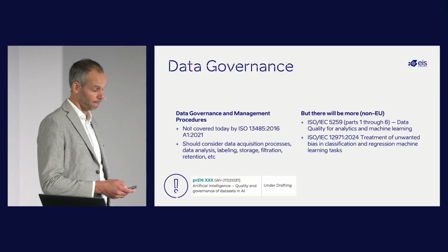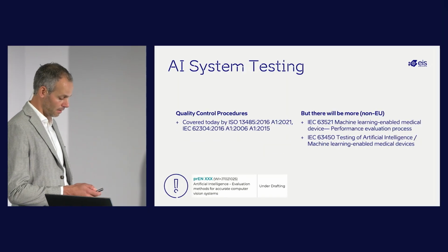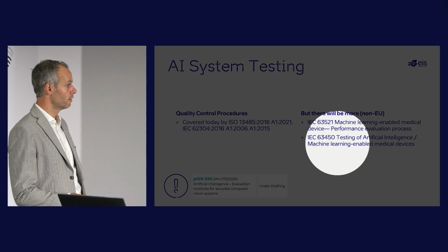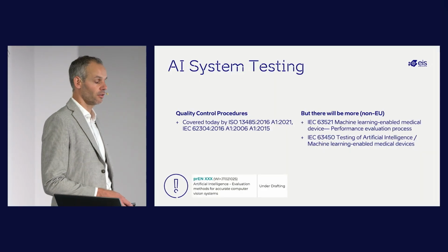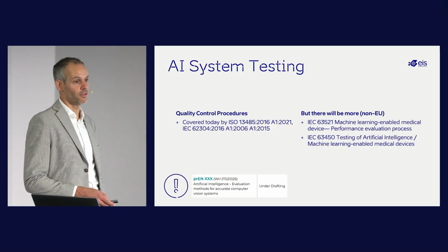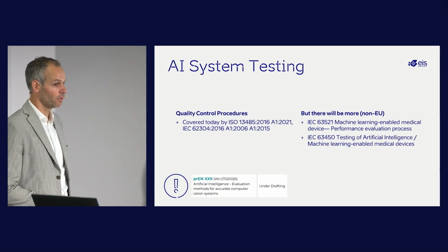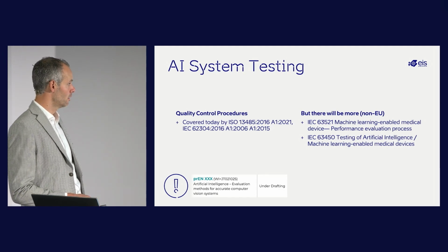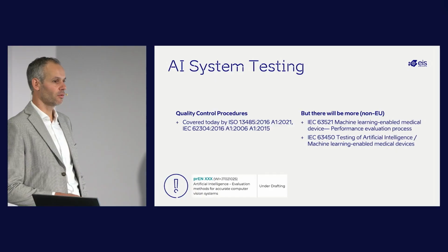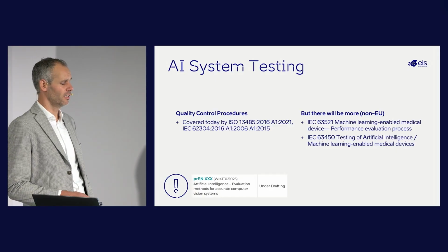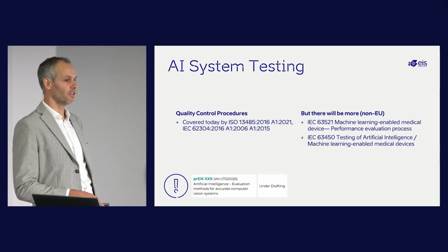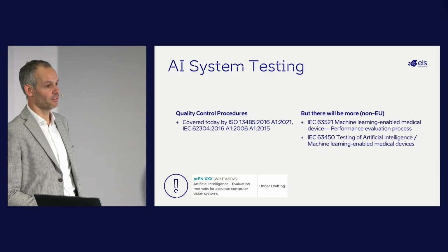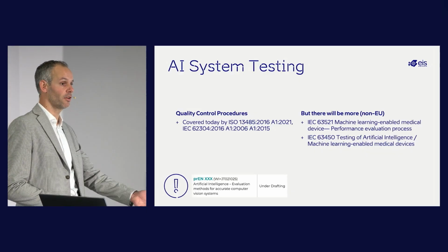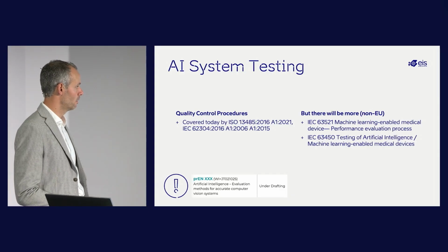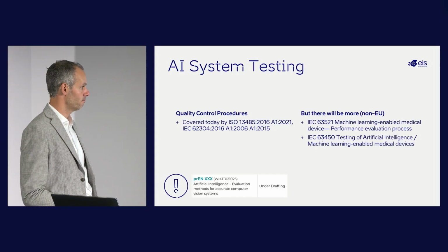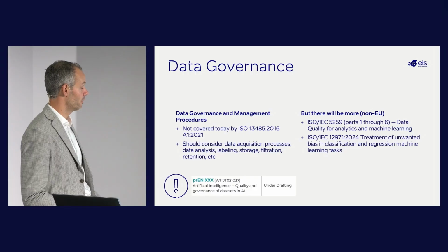What's the timeline of the testing regulation? Is it final? You mean this standard? Yes. Yeah, so currently we're in the final draft, so I expect it to be published somewhere within the next half year. So that should be quite fast. But it's based on another standard, which is the 29119, I think, which is an ISO standard, which is deemed not applicable to medical devices. So that was the base template, and then we adapted it for medical device use. But again, the amount of standards is actually crazy.